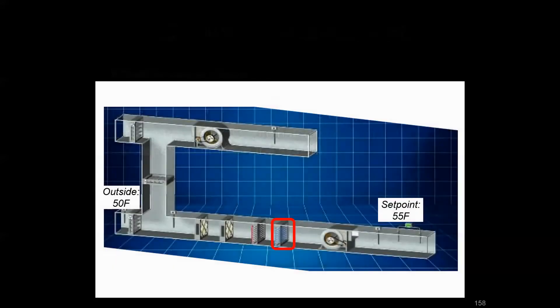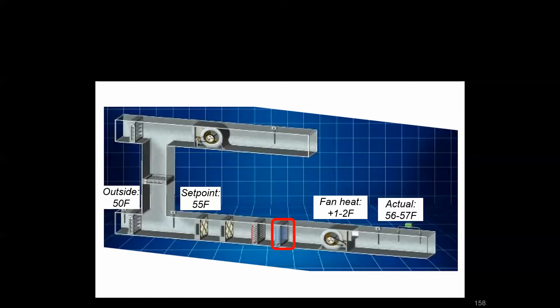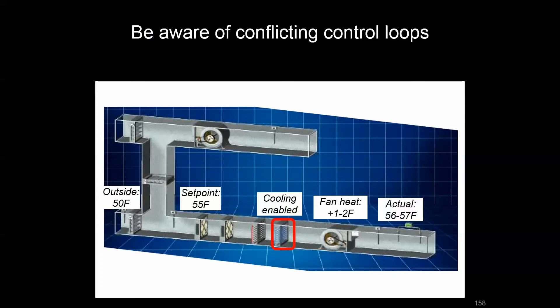What do we mean by good coordination of set points? Say it's 50 degrees outside and you're trying to hit a supply air set point of 55 degrees — you shouldn't need to use your cooling coil. But if you set it right at 55, the supply fan doing work on the air will add a degree or two, giving you 56 or 57 degree supply air, which may enable your cooling coil unnecessarily. Because of this poor set point coordination, you're using more energy than needed.